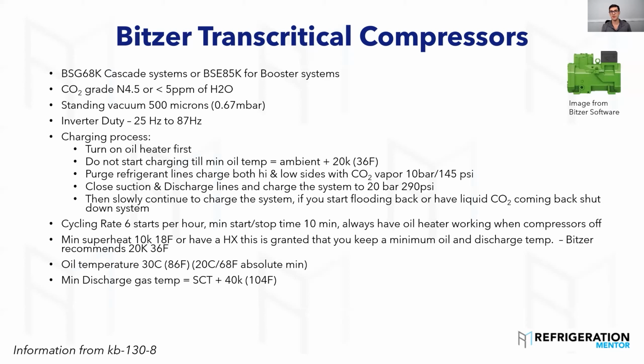Minimum discharge temperature is your condensing temperature plus 40K. That's the minimum discharge temperature they give. Once again, I've only seen this in the Bitzer manuals, but I'm sure it's in other manuals as well. Maximum discharge temperature is 140C, 284F. This is a little different than Copeland, which we'll go through, but it's something you need to be aware of. When you start getting above 300 with POE oil, it starts to lose its lubrication properties. When you get up to 330 or 350, I can't remember right now, it starts to break down. I've seen this before. If you start running that hot in your system, you've got to remember your oil separators only pull oil out of the refrigerant at certain temperatures.